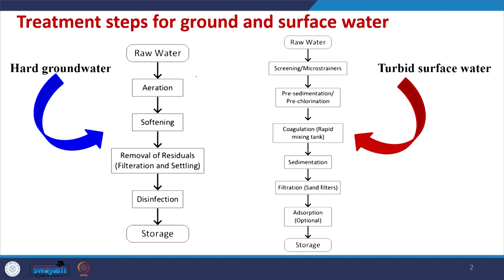For ground water, the first step is aerating the water. This is done because ground water coming from a confined aquifer may still contain some gases, or the amounts of oxygen and CO2 may be either lower or higher than required. Aeration is done to remove any toxic gas like H2S if present, and also to equilibrate the water with respect to the amounts of oxygen and CO2. Sometimes softening may or may not be required depending upon the presence of ions like calcium and magnesium.